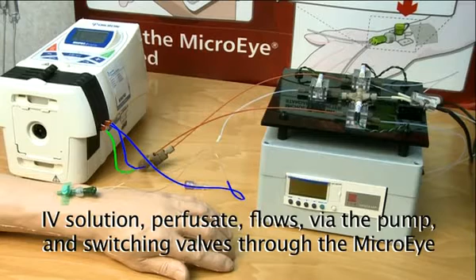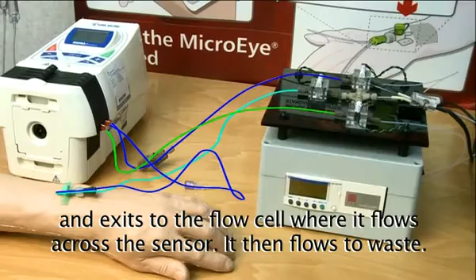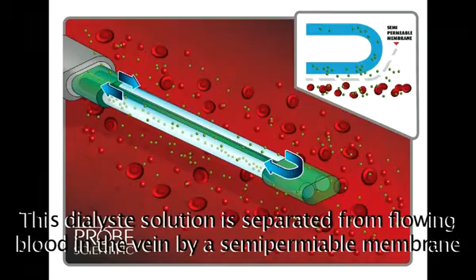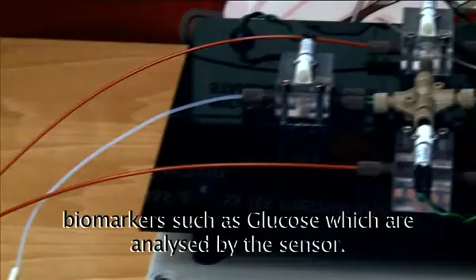IV solution perfusate flows via the pump and switching valves through the MicroEye and exits to the flow cell, where it flows across the sensor. It then flows to waste. Flow rates are low, typically between 10 and 100 microliters per minute. The dialysate solution is separated from flowing blood in the vein by a semi-permeable membrane, across which diffusion occurs. The solution then contains small molecular weight biomarkers such as glucose, which are analysed by the sensor.